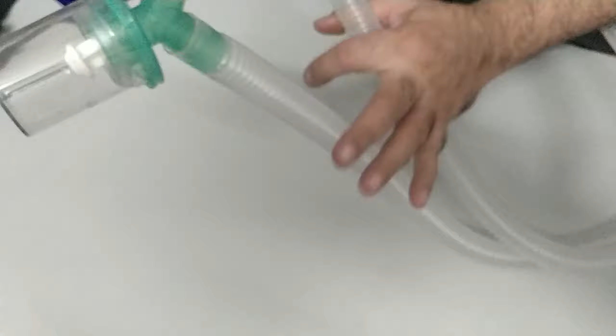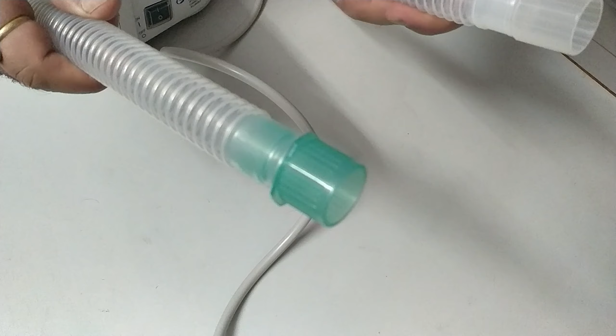The circuit will have this kind of look. It has a double trap, the inspiratory and expiratory limbs, and the Y piece. Now you have to connect the inspiratory limb to the outlet of the chamber. There is also a port for the feed. If you have a sterile bottle feed, this is the port you open and then insert the pin; otherwise you keep it closed if you are feeding manually through the inlet. Now the other end of the humidifier you have to connect back to the ventilator. This is the expiratory limb and this is the inspiratory limb, the white one. Now you connect both ends to the ventilator, and now it starts working.